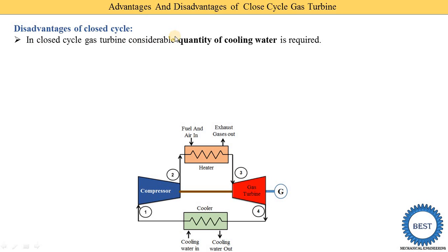The next topic is the disadvantages of closed cycles. The first disadvantage is that a considerable quantity of cooling water is required. Here you can see in this cooler, cooling water flows in and out to absorb heat energy from the working fluid. Due to this water requirement, closed cycle gas turbines are not used in aircraft, meaning aviation industries use only open cycle gas turbines.